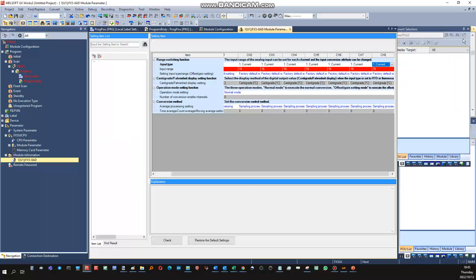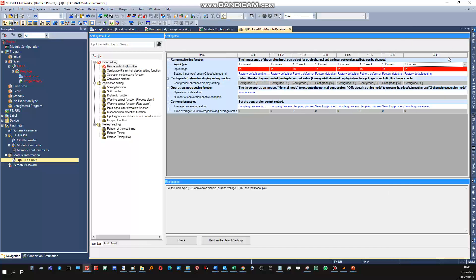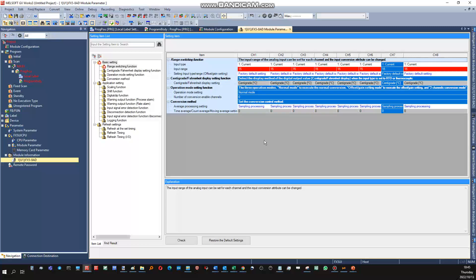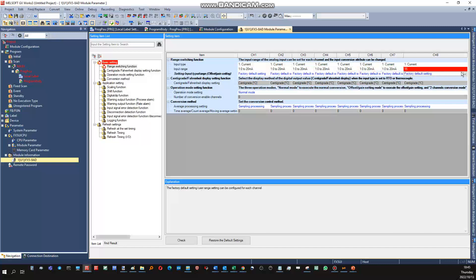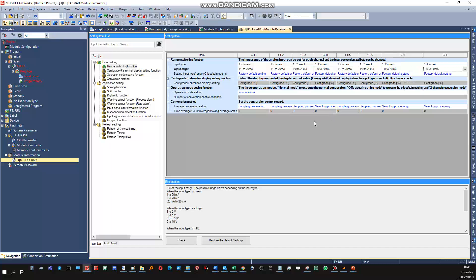Let me just unpin these windows on the side to enable more space. Now, input ranges can be changed. We said current, so let's go from zero to 20 milliamps. As you can see, the famous 4 to 20 milliamps is also there, but for simplicity we will use zero to 20, although for obvious reasons the 4 to 20 would be the superior option for practical field applications. These will be the basic settings to enable the analog inputs.